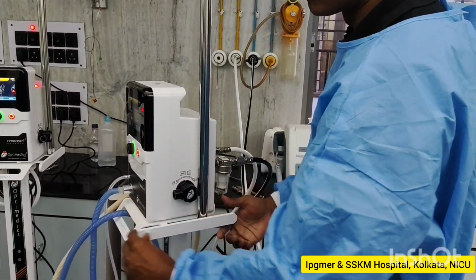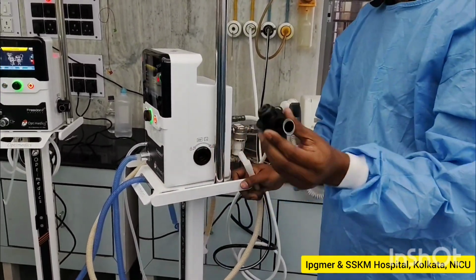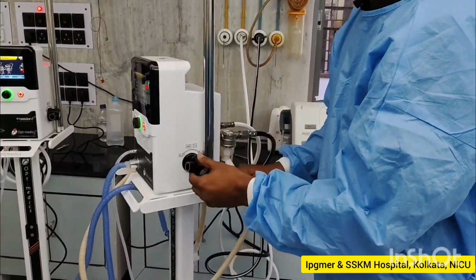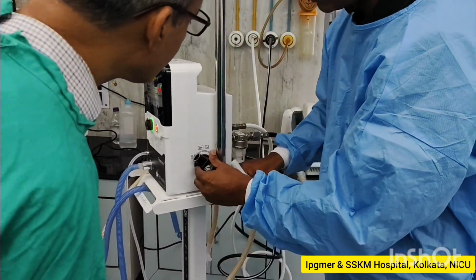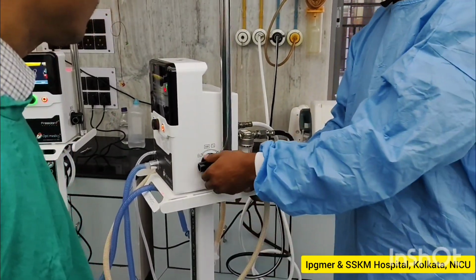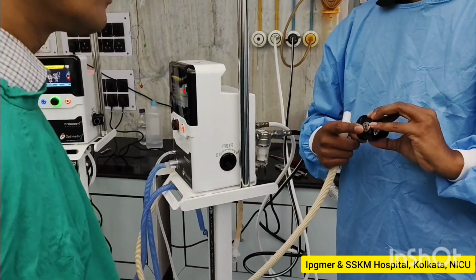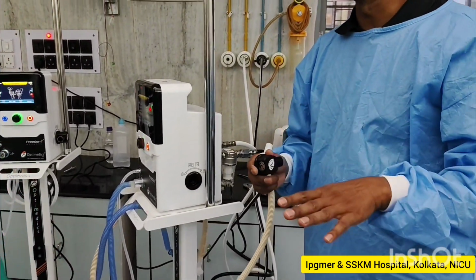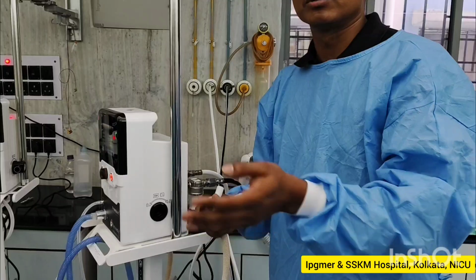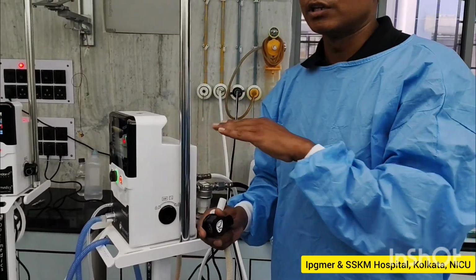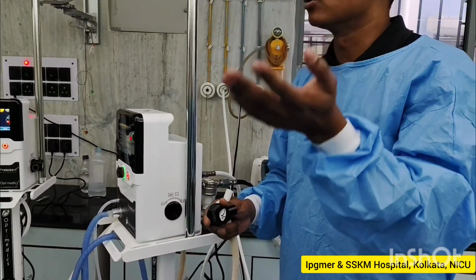This exhalation valve is autoclavable, you can even ETO autoclave it, and it is easily removable and attachable. You have to match this triangle and lock it. Simple. We have even provided a mechanical safety in the exhalation valve. So in any condition, if pressure shoots above 30 cm H2O, the machine will limit the pressure. It will never allow the baby to breathe above 30 cm.